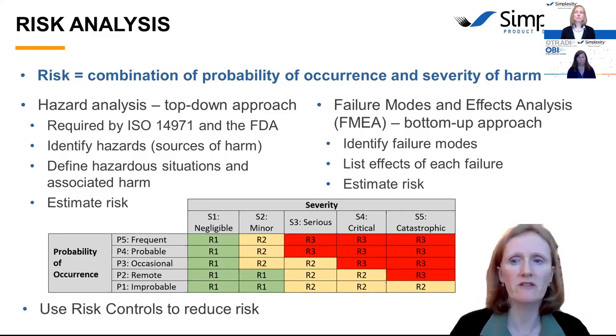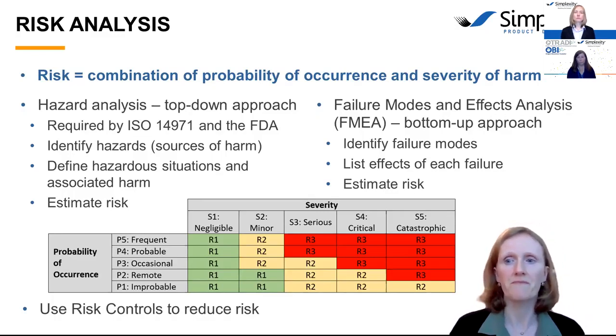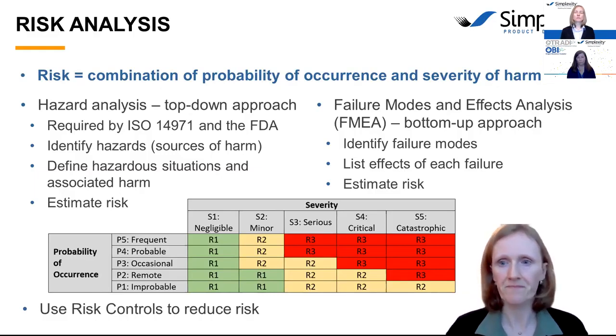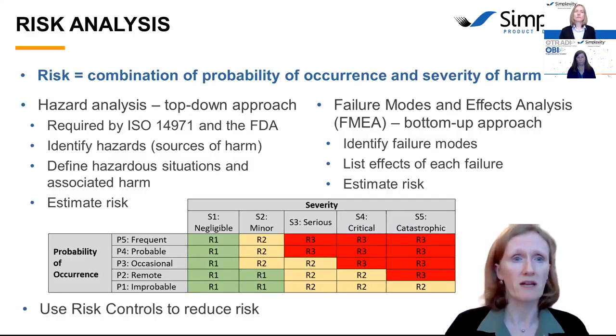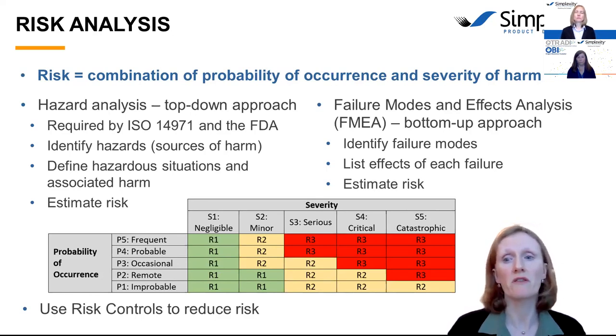But in medical devices, risks are not solely a function of failures. For example, an FMEA can't find missing things in your design because you've started already with the design. So FMEA is better as a reliability tool than as a purely risk management tool. However, it is a useful tool and can be very effective when used together with a hazard analysis.